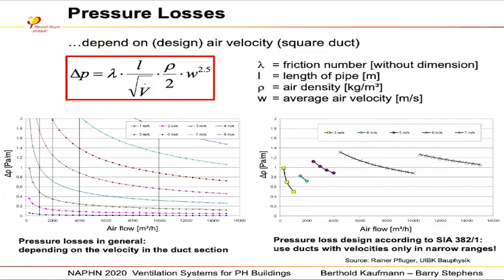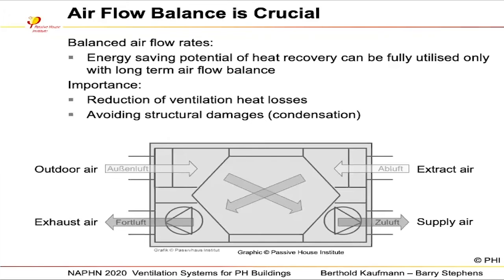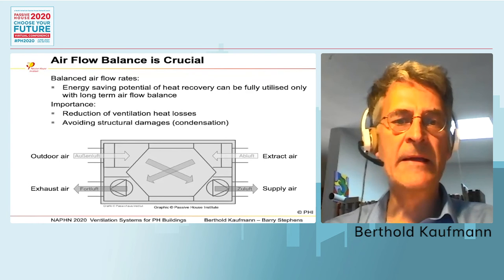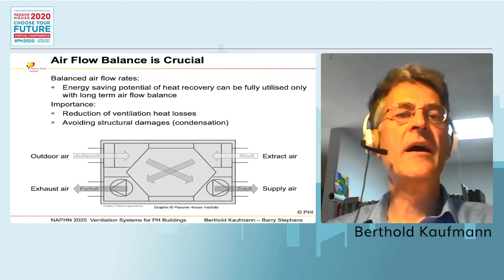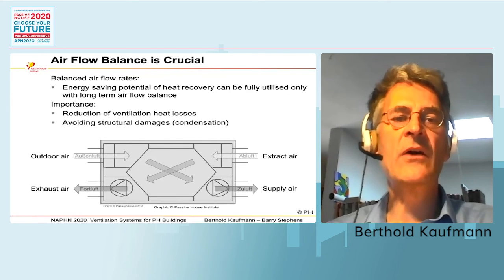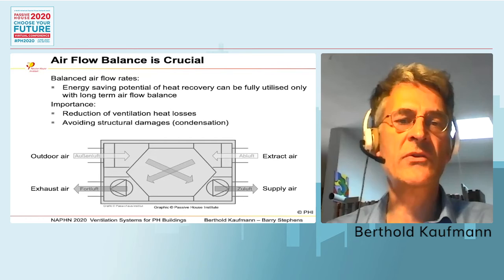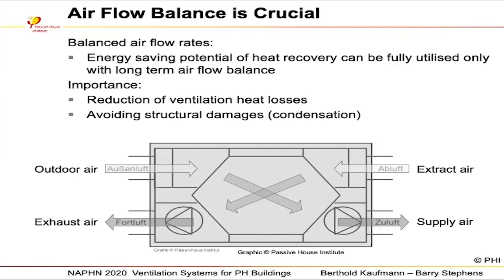So take only the range that you see on the right-hand side, and not too much. And check for short ducts and large enough diameters, and care for pressure losses for each element you have in there. Okay, the next topic is the airflow balance. As I mentioned already, now into some detail, we want to have a balanced airflow, so outdoor air coming in and exhaust air going out should be the same.